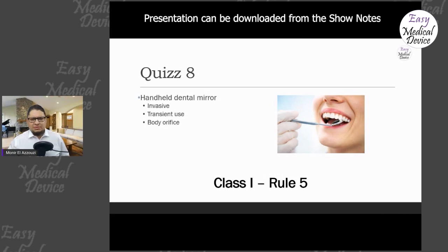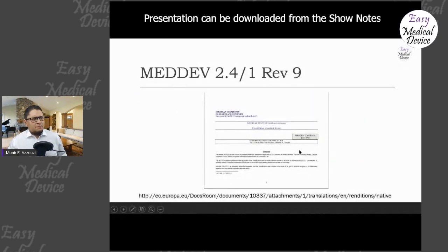So it's invasive. So it means that you have to go to the section of invasive devices. Here, Rule 5: all invasive devices with respect to body orifice other than surgically invasive devices, which have no connection with an active device or which are intended to connect with a class 1 active device, are classified as class 1 if they are intended for transient use. So here it's transient use. So here it's Rule 5, class 1. This is also something that you can find in a certain document called the MedDev 2.4/1 Rev 9. This is a document that we mainly use, a guidance for classification.